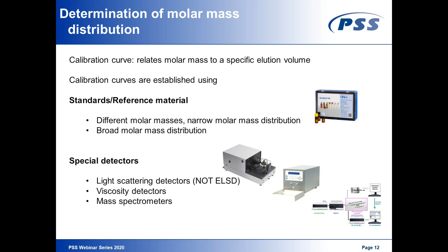All these detectors will allow us to measure the molar mass at a specific elution volume. Important is that you do not confuse an evaporative light scattering detector with the light scattering detector shown here, which is a light scattering detector in solution, because evaporative light scattering detectors are basically concentration detectors. You cannot measure the absolute molar mass using an evaporative light scattering detector. For this, you would need a light scattering detector in solution.